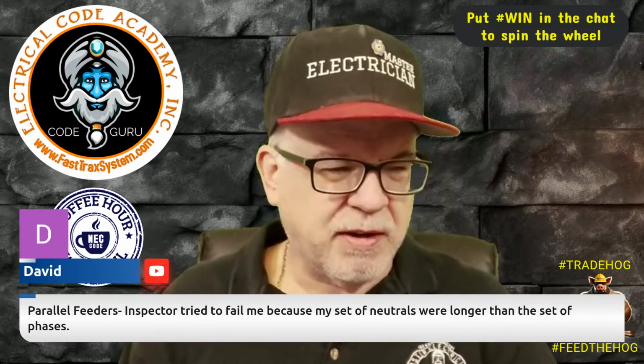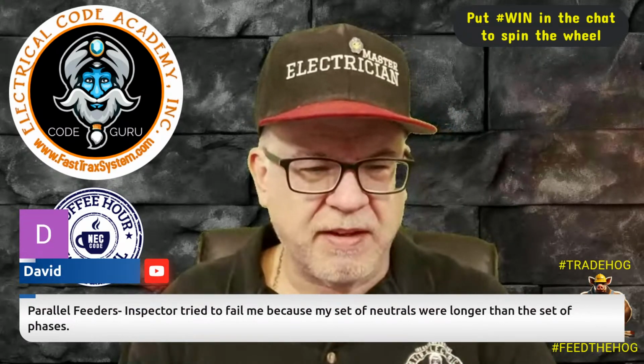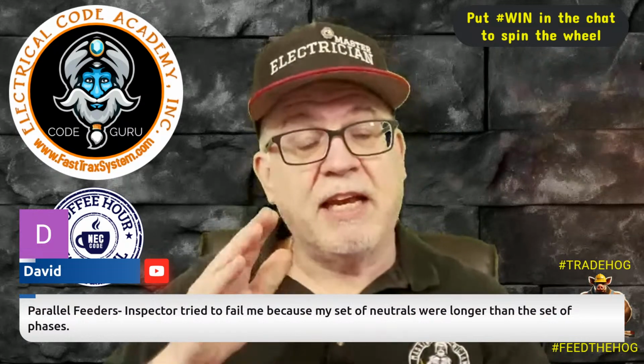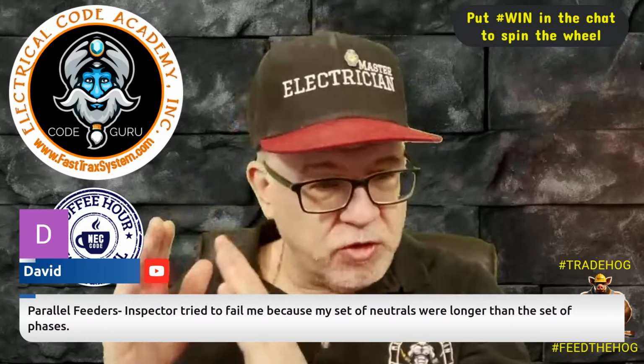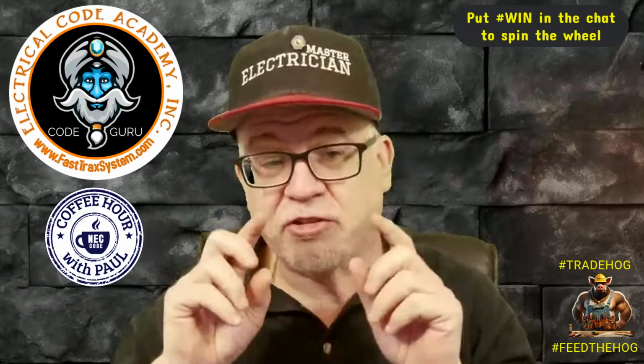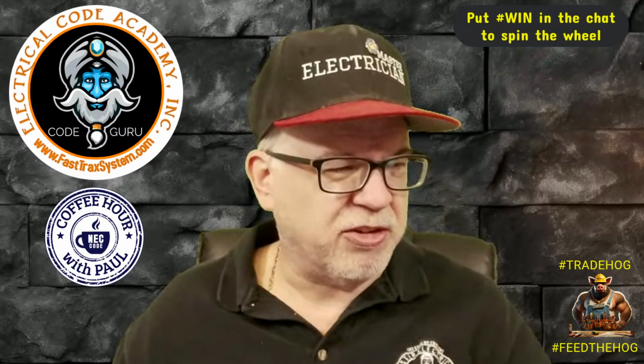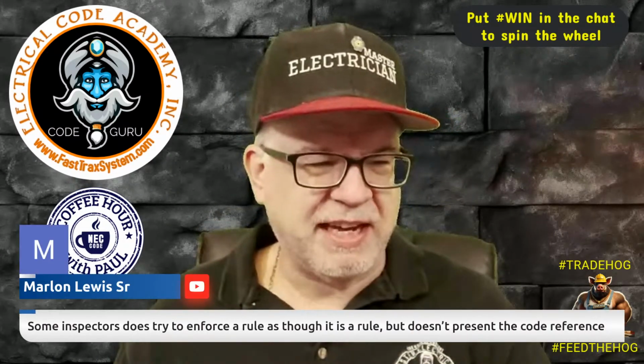David says, parallel feeders, inspector tried to fail me because my set of neutrals were longer than the set of phases. Again, it's different. So the neutrals get treated differently. You say he tried to fail you. Was he successful? Did he make you do anything? Let me know. How'd you fight that one?